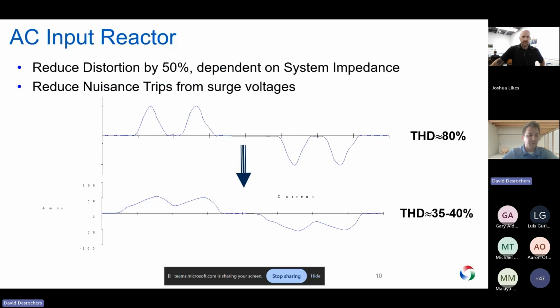And just kind of as a view, if we were to place one of these harmonic reactors in front of the drive, we go from these current spikes, which are very characteristic of a VFD running across the line, to something that's a little bit smoother and less jarring to your facility power. It's going to impact the neighboring facility, neighboring hardware a little bit less now that we add on this AC input reactor. So again, this could be a whole other PowerPoint. This is like a first line defense of using an input reactor to try to lower your harmonic distortion there. And it is the go-to solution in a lot of cases.